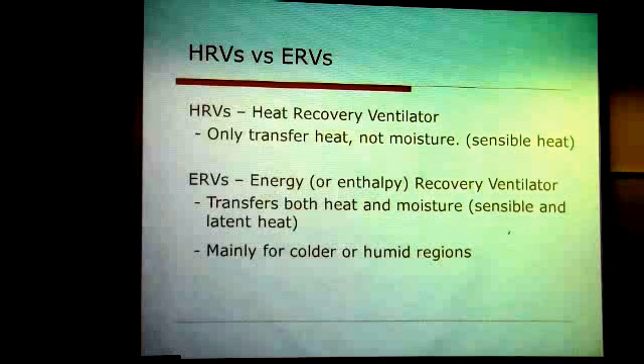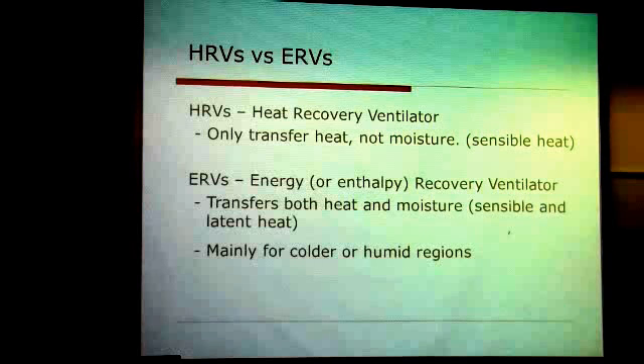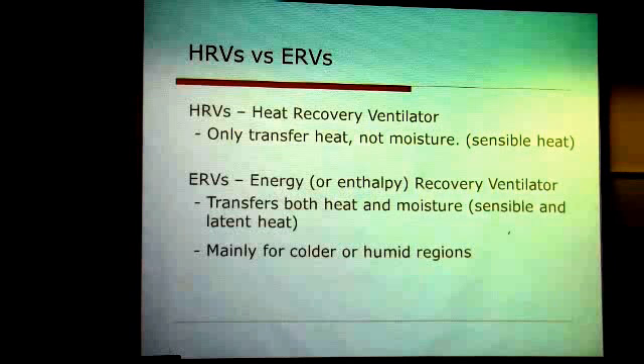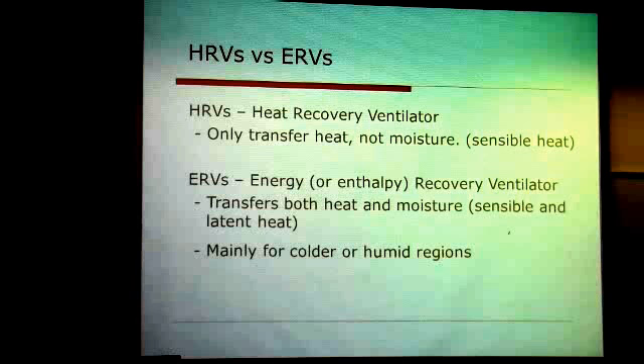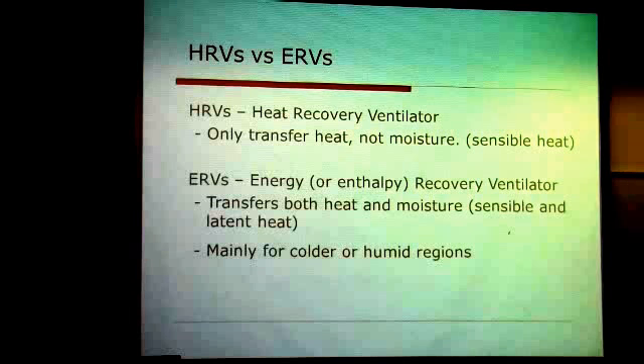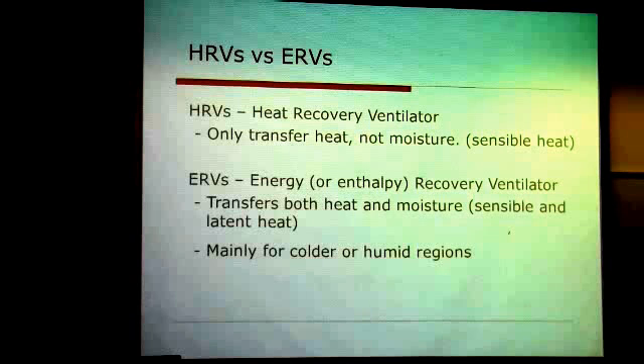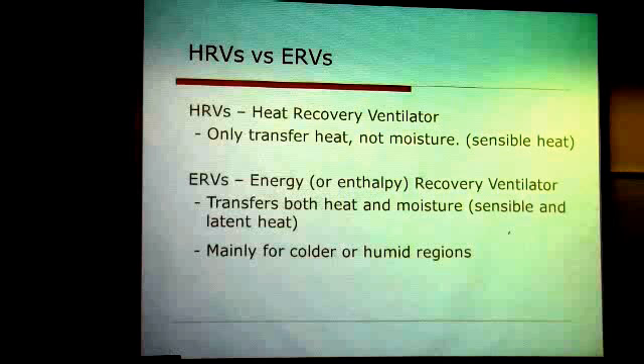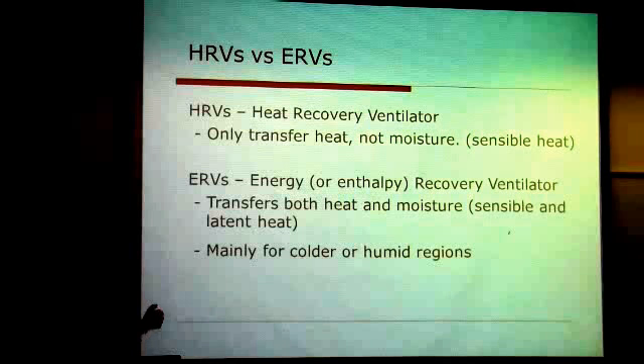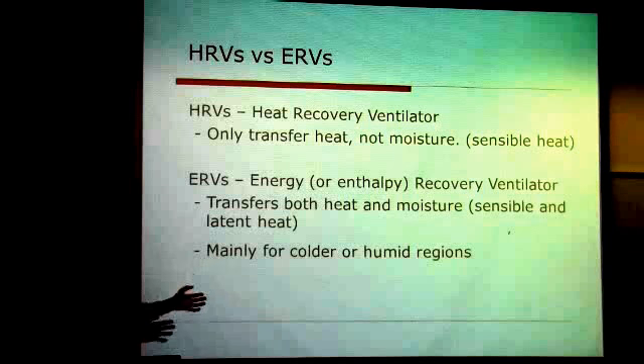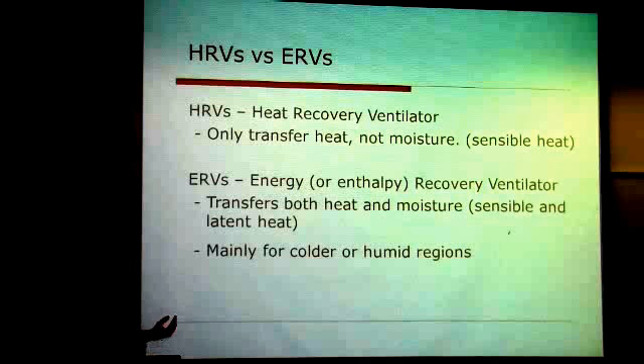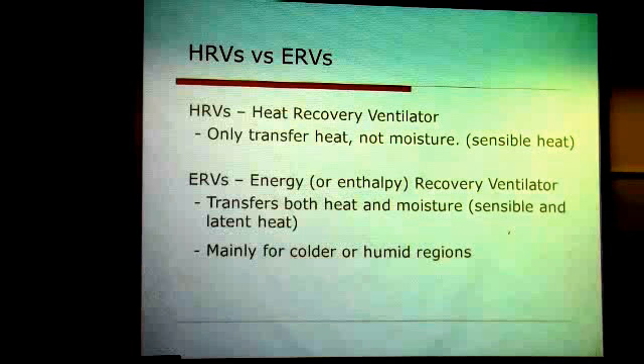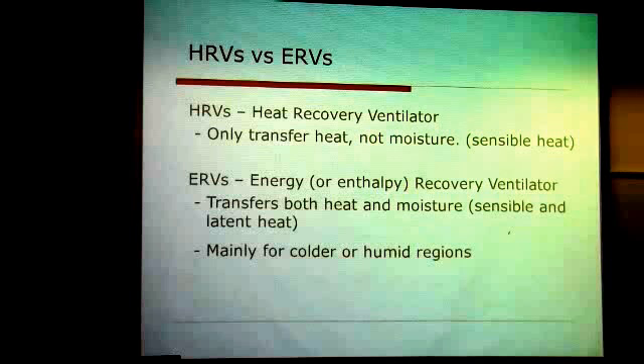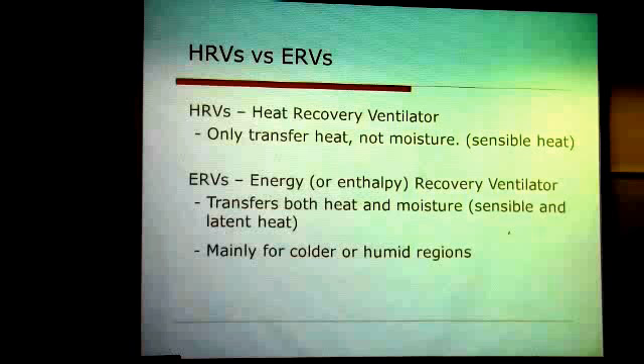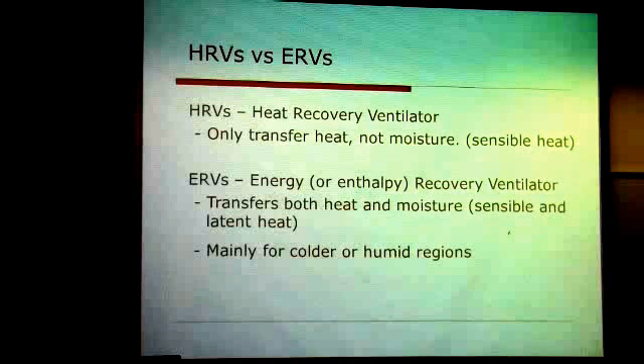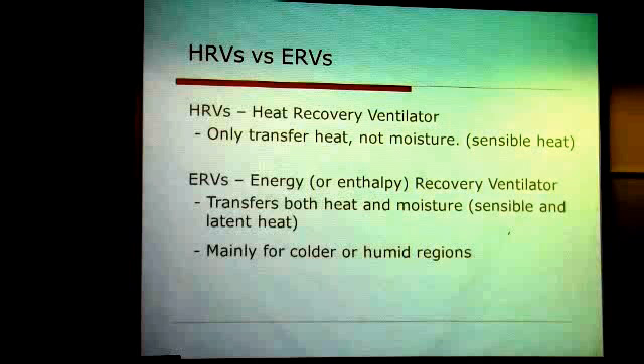And then you'll hear about ERVs. On the East Coast, they use mainly ERVs. With HRVs, you're only transferring the heat, so they're solid panels in the heat exchanger, whereas an ERV has a semi-permeable membrane, using similar technology to fuel cells, but it allows moisture to pass through, usually about 60% of the moisture. So if you're in a hot, humid climate, it keeps 60% of that moisture outside. You don't want to be bringing 90% humid air back inside when it's less humid inside. So it's transferring some of that humidity to the exiting stream, but it still doesn't mix the flows. It's just allowing moisture, not the actual air.